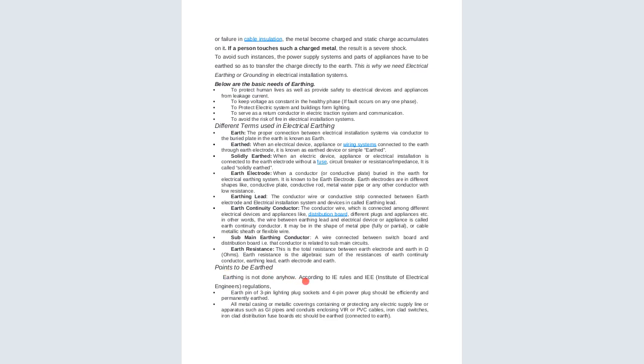So, points to be earthed. Earthing is not done anyhow. Of course, you cannot just do the earthing anyhow. There are special locations or special areas where the earthing is done. According to the IE rules and the IEE, Institute of Electrical Engineers, regulations, the earth pin of the 3-pin lighting plug and the 4-pin power plug should be efficiently and permanently earthed.